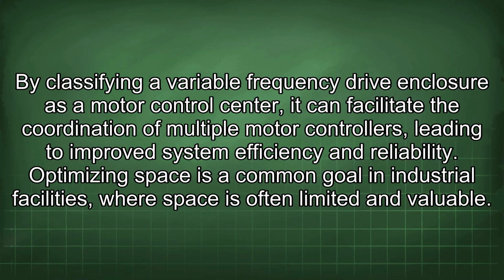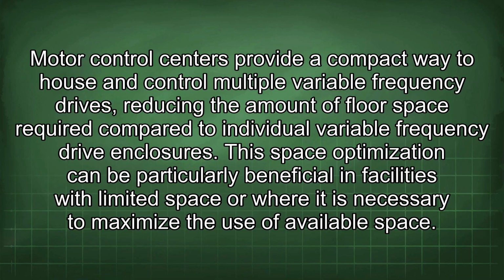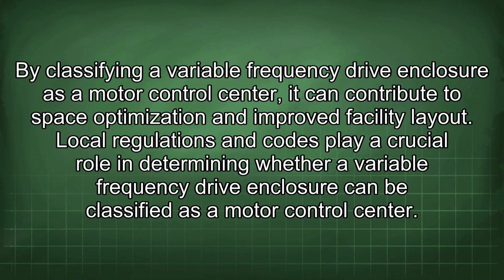Optimizing space is a common goal in industrial facilities, where space is often limited and valuable. Motor control centers provide a compact way to house and control multiple variable frequency drives, reducing the amount of floor space required compared to individual variable frequency drive enclosures. This space optimization can be particularly beneficial in facilities with limited space or where it is necessary to maximize the use of available space. By classifying a variable frequency drive enclosure as a motor control center, it can contribute to space optimization and improve facility layout.